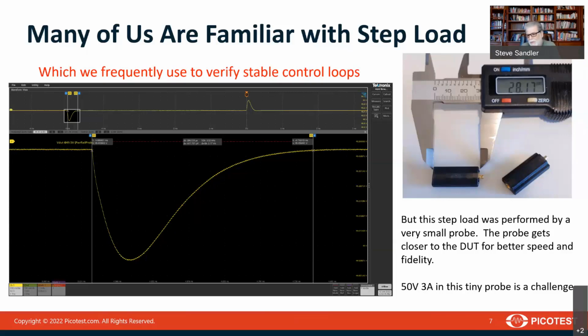But it wasn't easy to do because we needed to do, first of all, a 3 amp step on a 65 volt power supply. So that's a pretty large step. The bandwidth of the step had to be up to 700 megahertz, which means that we couldn't use any cables. And so we needed to put it into a probe. And you can see this probe here that's just a little over 1 inch long. That's actually the step loader, and that's actually doing the, in this case, 50 volt 3 amp step.